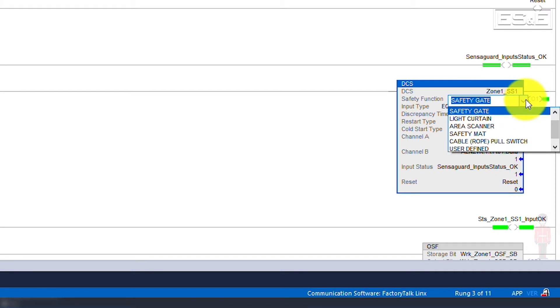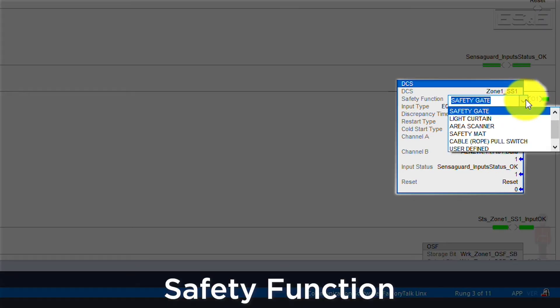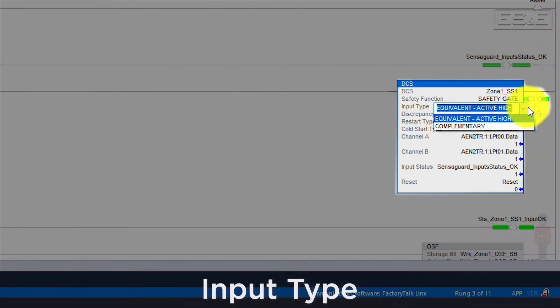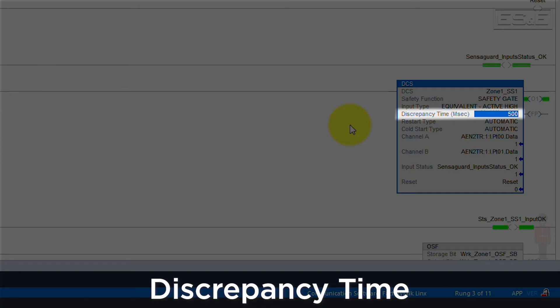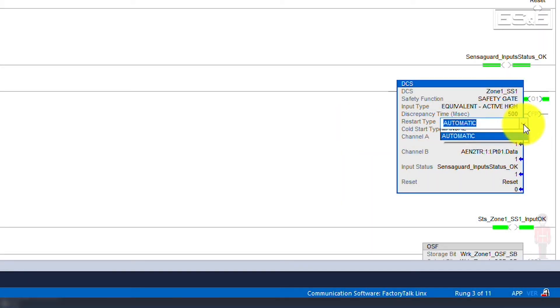The safety function allows you to show the end device function you are programming, such as an e-stop. The input type allows you to pick the two signals that will be monitored — high or low — and if they will be the same signal or opposing. Discrepancy time is the time difference allowed for one signal to change state compared to how long the second signal takes to change state. Lastly, the reset can be configured as automatic or manual. Since integrated safety has been improving and more equipment has been utilizing safety controllers, Rockwell has improved upon its legacy and more specific safety instructions. A good example is the e-stop instruction, which can be replaced by the DCS instruction. The legacy instructions will still work, but have limitations that can be overcome when using the preferred instructions.